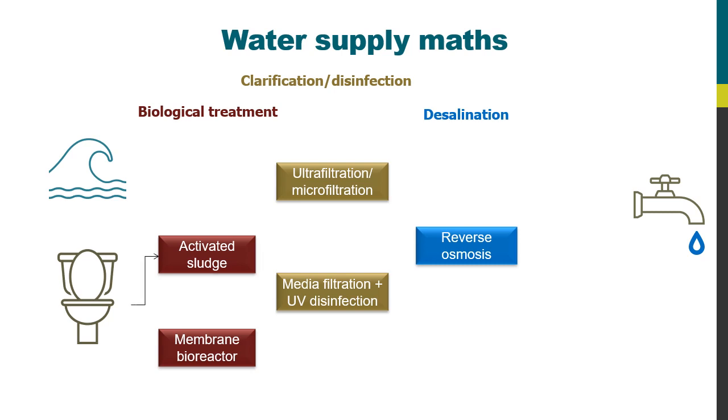Prior to desalination, it would, like seawater, need to be filtered by either of these two options before going to the RO stage. The other option is to use an MBR instead of CAS. This will produce a clarified water which then no longer needs to be filtered. So the filtration disinfection step is unnecessary in this case. And once again, the RO permeate will be drinkable but will require the same post-treatment as for the seawater feed.